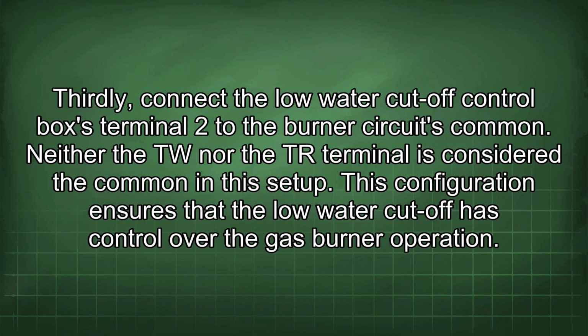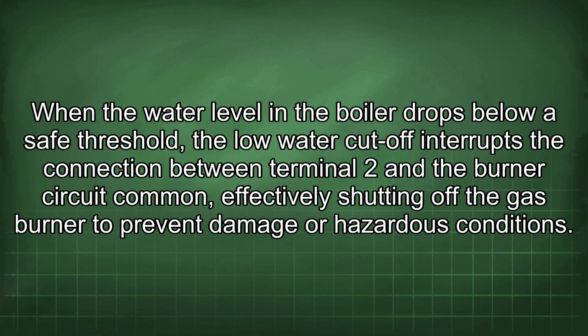Thirdly, connect the low-water cut-off control box's terminal 2 to the burner circuit's common. Neither the TW nor the TR terminal is considered the common in this setup. This configuration ensures that the low-water cut-off has control over the gas burner operation. When the water level in the boiler drops below a safe threshold, the low-water cut-off interrupts the connection between terminal 2 and the burner circuit common, effectively shutting off the gas burner to prevent damage or hazardous conditions.